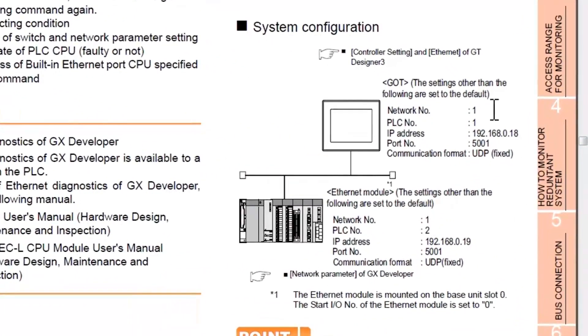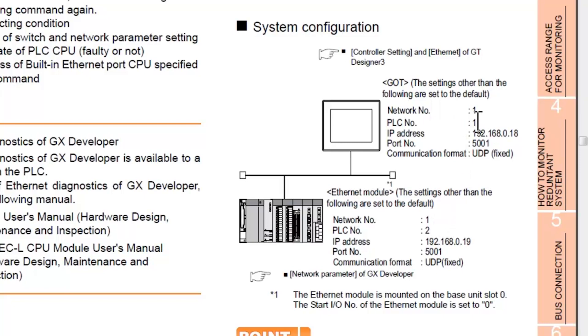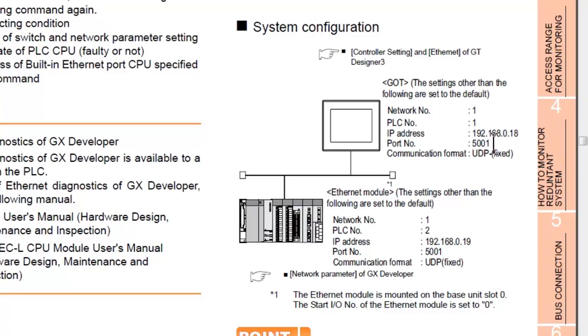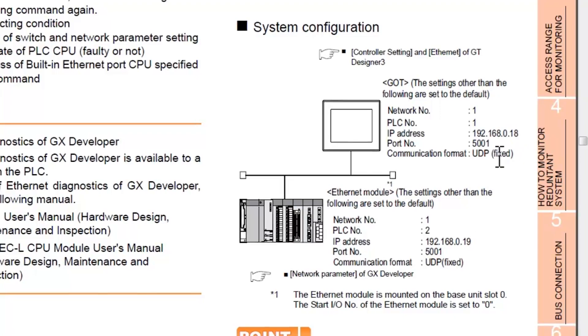So you have your network number matching the network number on the PLC. And for PLC number, the PLC number for the GOT is different from the PLC number for the Ethernet module. Very important. And again, you can see these IP addresses are similar except for the last digits, 18 and 19. Leave the port number alone and leave the communication format alone.